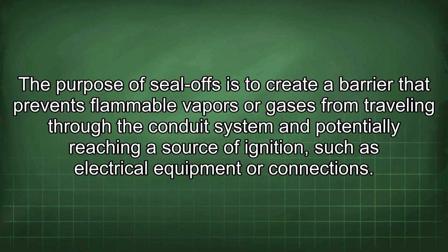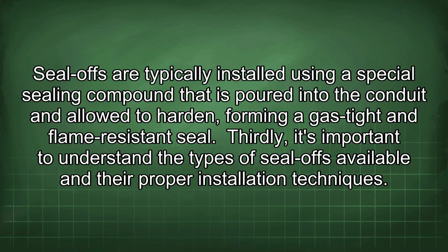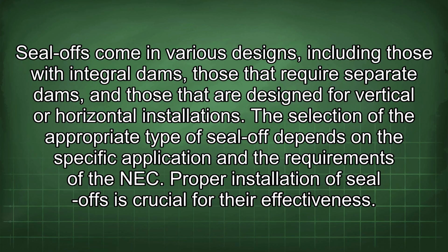The purpose of seal-offs is to create a barrier that prevents flammable vapors or gases from traveling through the conduit system and potentially reaching a source of ignition, such as electrical equipment or connections. Seal-offs are typically installed using a special sealing compound that is poured into the conduit and allowed to harden, forming a gas-tight and flame-resistant seal. Thirdly, it's important to understand the types of seal-offs available and their proper installation techniques. Seal-offs come in various designs, including those with integral dams, those that require separate dams, and those that are designed for vertical or horizontal installations.